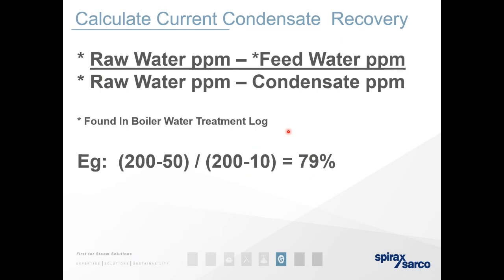Good question. Anything that contains steam, you don't want it to lose the heat. So I would suggest it has to be insulated. We would insulate our MFP, for instance, and that's a condensate unit, for that very reason: we're trying to maintain as much heat as possible. So a flash unit is no different. When I say frame, I mean flash, flash vessel.